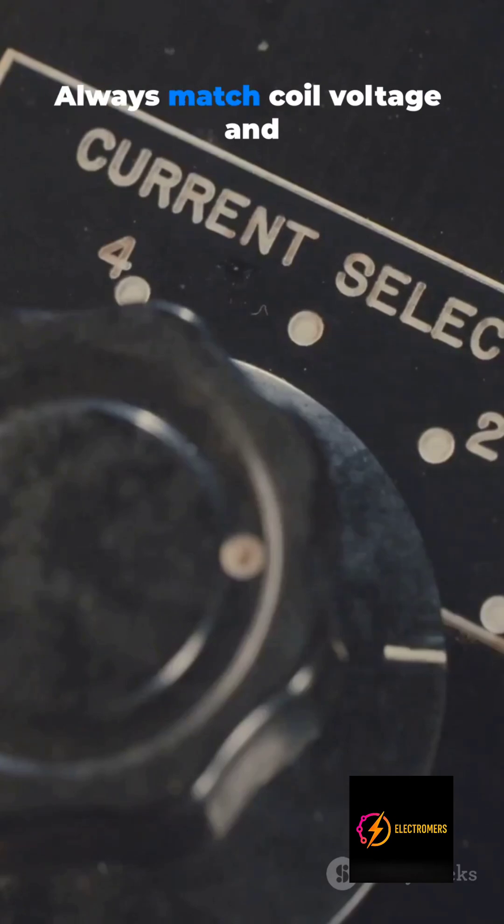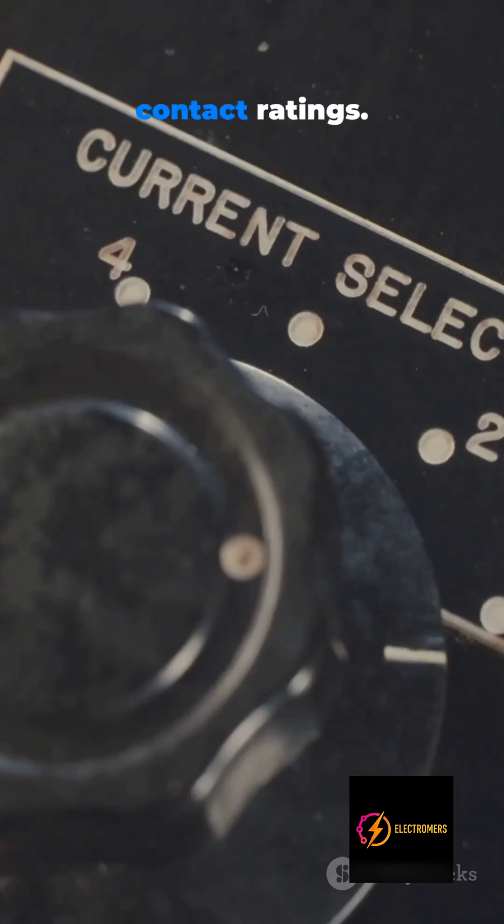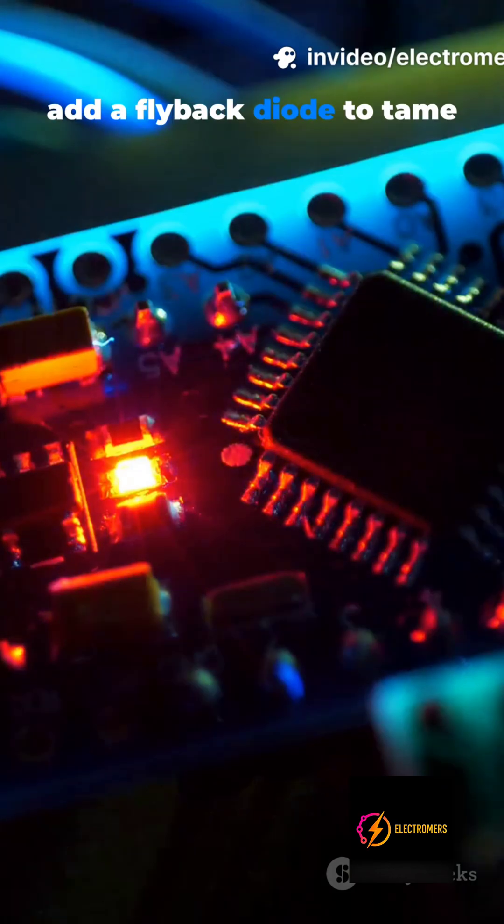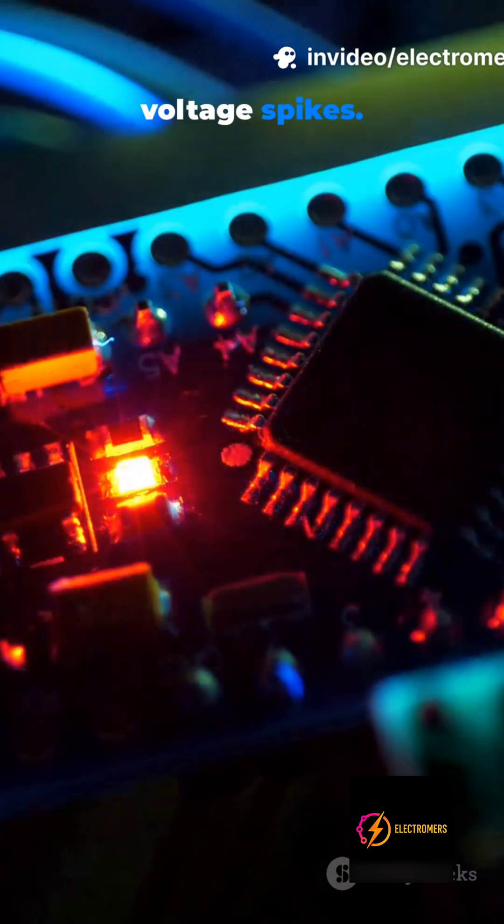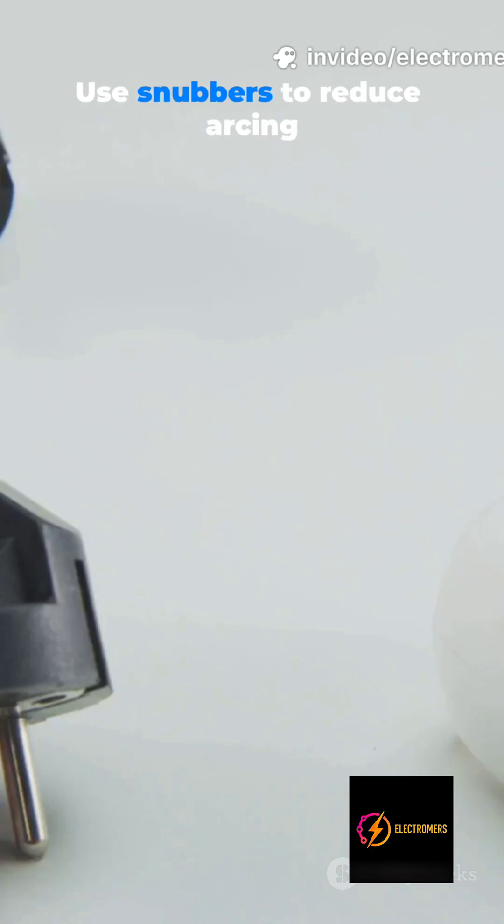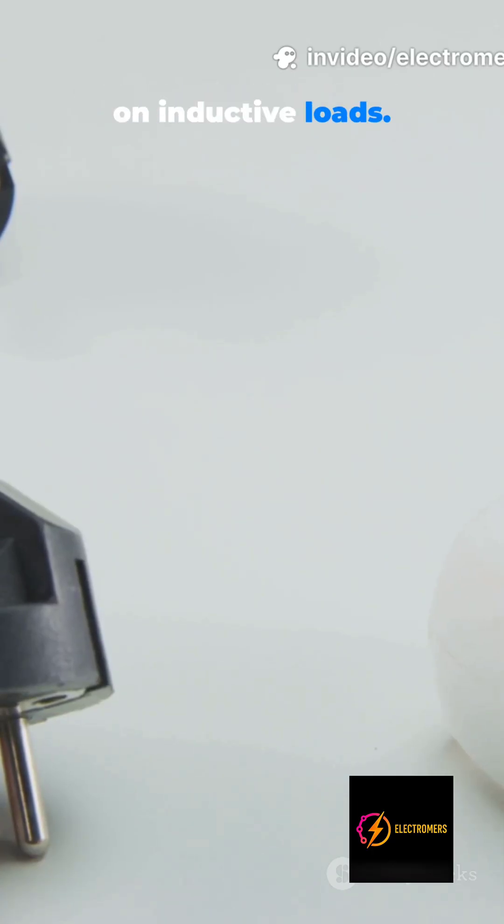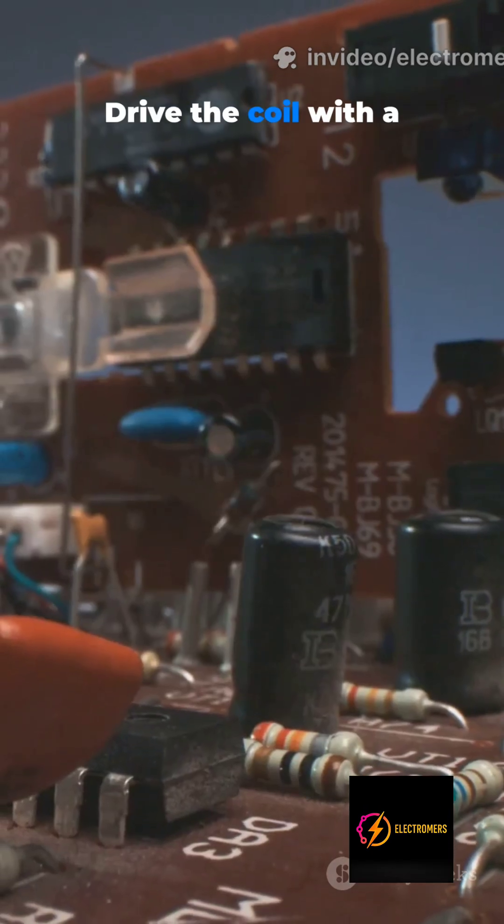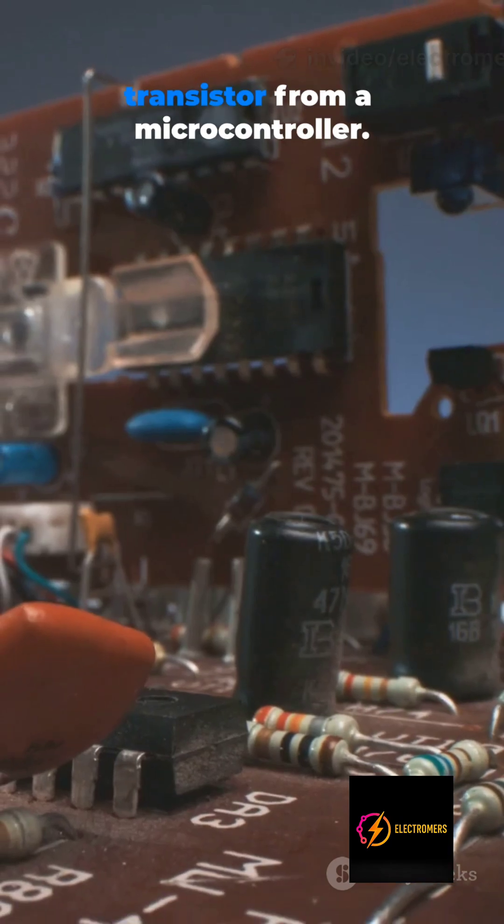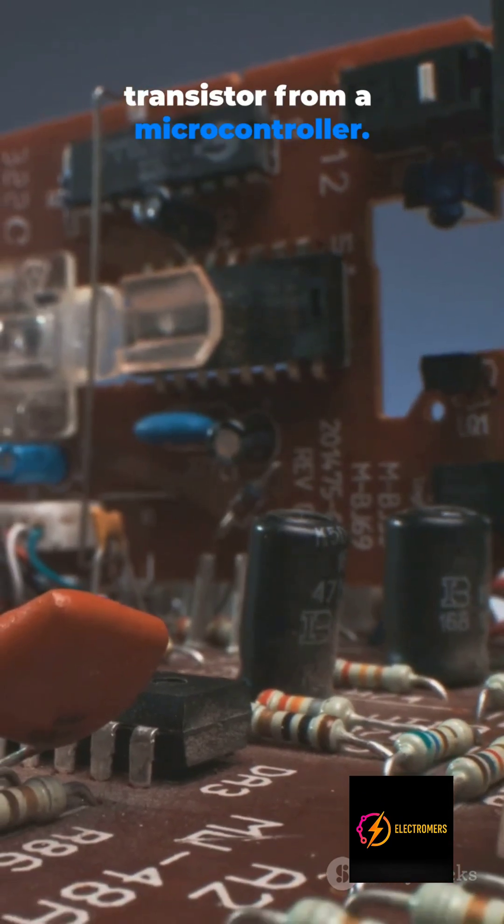Always match coil voltage and contact ratings. Coils are rated for DC or AC use. On DC add a flyback diode to tame voltage spikes. Use snubbers to reduce arcing on inductive loads.